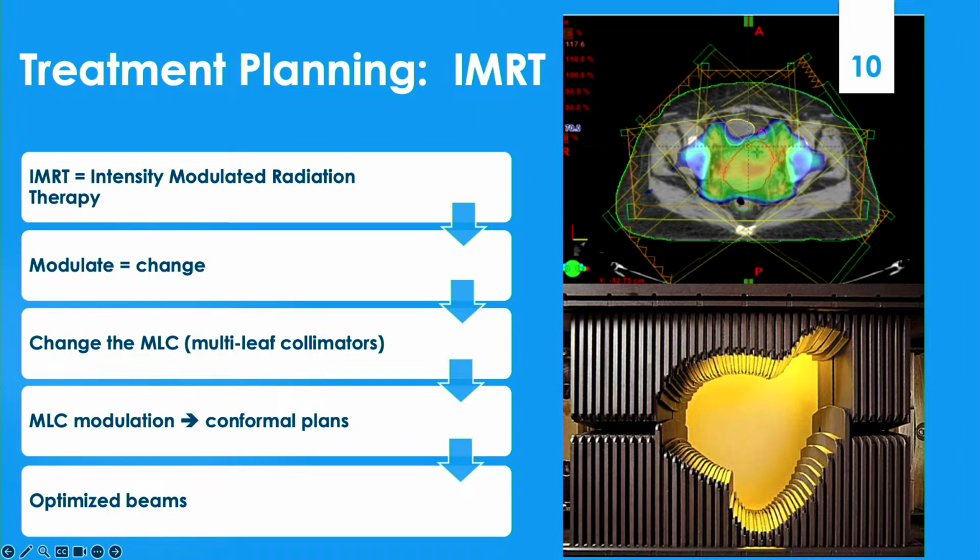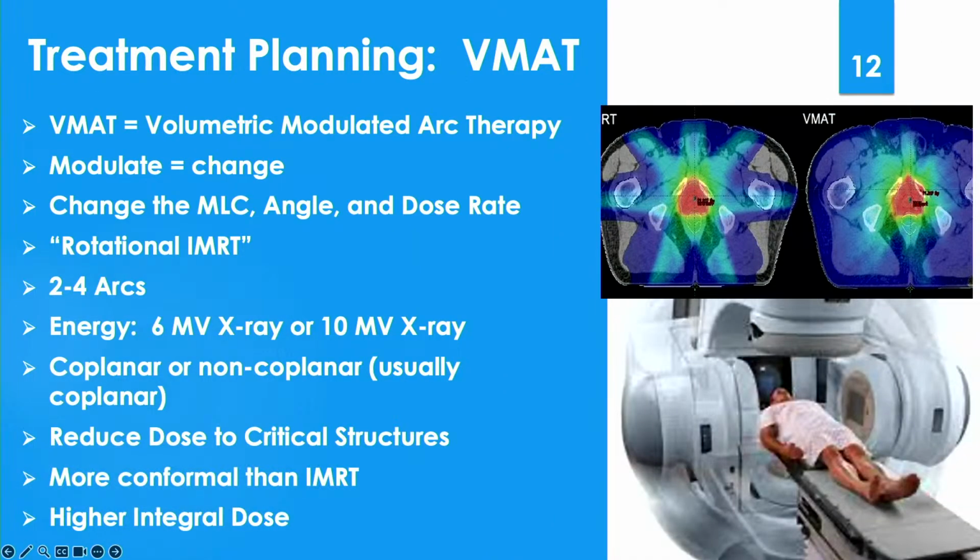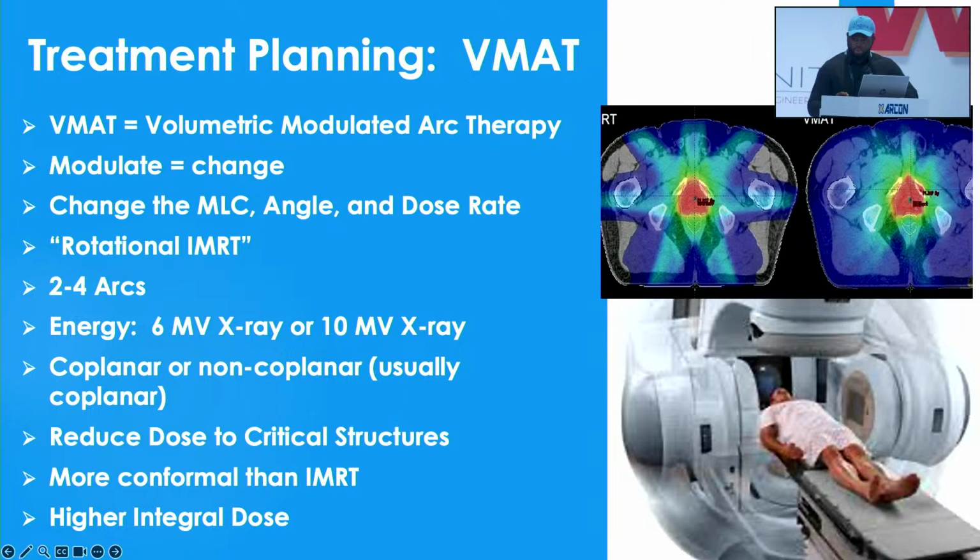And then the IMRT. So with this machine, we're able to do IMRT now, unlike when we had the old machine. As I said, we have the Millennium 120 MLC. Next slide, please. And then the VMAT, which gives room for more conformality of the beams. Because we have the VitalBeam, we're able to do both coplanar and non-coplanar plans. Next slide, please.